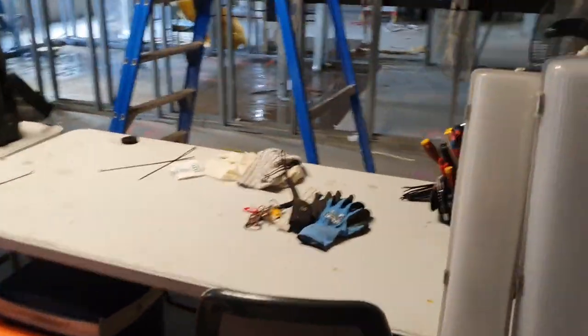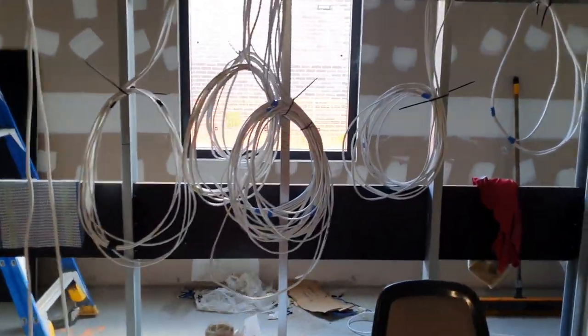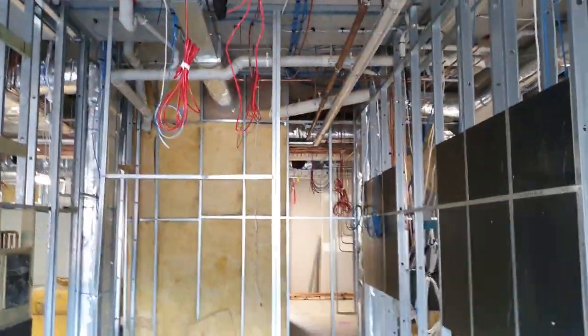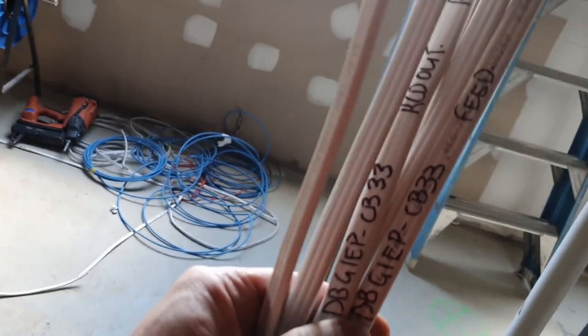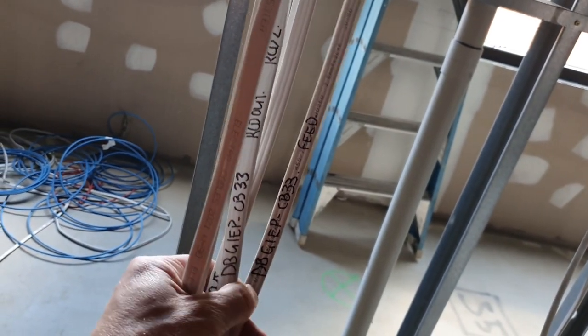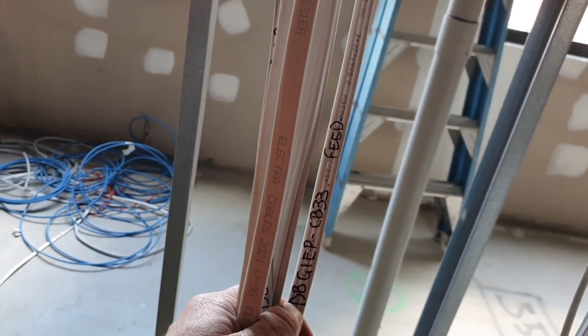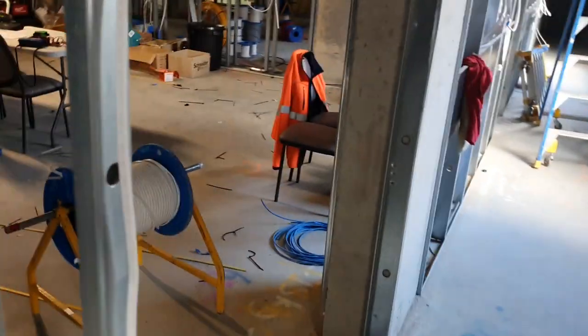This is our messy room with odds and ends but all cables are where they need to be. Today I was working on this room - all cables are dropped down in the walls where they need to go. In the coming week I need to start running steel conduit to protect the un-RCD side. In Australia, if a cable is on an RCD it can run in a wall cavity with no protection issues, but if it's not on an RCD you need to sleeve it in steel conduit and earth the conduit. That's probably the easiest approach - open to suggestions.